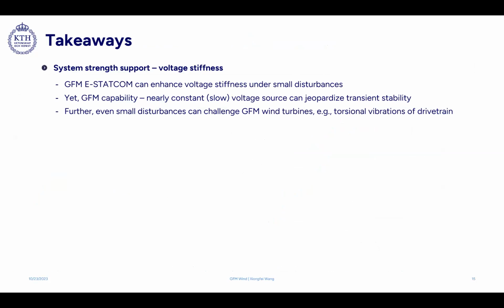Here are some takeaway messages. The first one is about system strength support regarding the voltage stiffness enhancement. The grid-forming STATCOM can enhance the voltage stiffness under small disturbances, but this kind of nearly constant voltage source can jeopardize the transient stability under large disturbances. So we have to change the slow voltage source to a fast voltage source to track the angle difference or to limit the power angle difference.